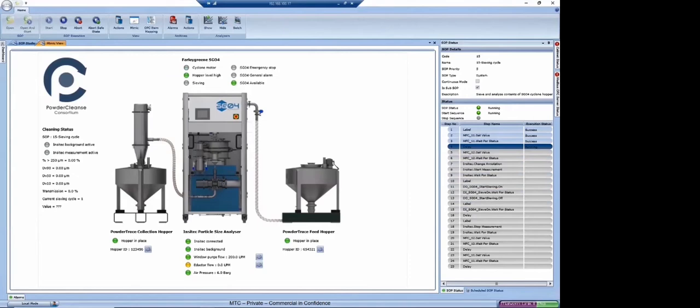After the cyclone motor turns off, stopping the powder transfer, sieving of the first sub-batch is started. With a configurable combination of mechanical and ultrasonic sieving, powder is conditioned by passing it through the sieving screens. Oversized material is collected and weighed in the oversized collection vessel, while in-specification material is pneumatically conveyed through the Insitec measuring cell and then finally to the collection system.